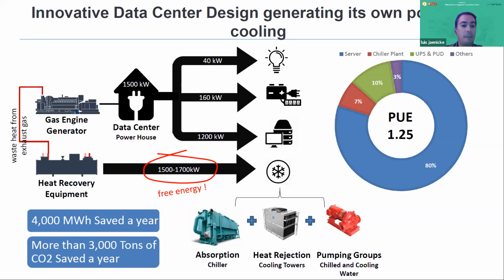So there is huge savings in electricity. If we consider 8,000 hours a year, roughly 4,000 megawatt hour of electricity is saved a year. And that accounts in this example for more than 3,000 tons of CO2. The CO2 emissions can drop compared with a traditional design by more than 40%, as Ravindra was mentioning before, not just because I'm saving a lot of power, but also because the emissions of a gas engine generator are lower than the average emissions of the power imported from the grid. So it's a very powerful solution, cogeneration for data center, to improve the PUE and reduce the CO2 emissions associated with this demand in power and cooling. Next slide, please.